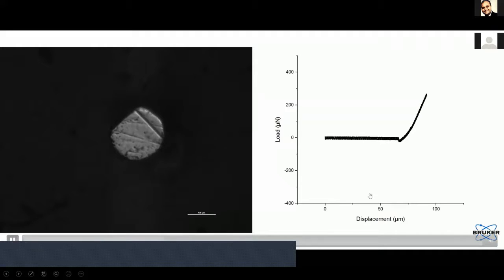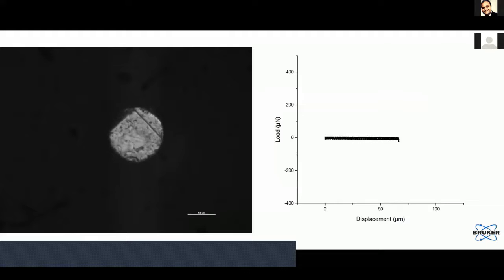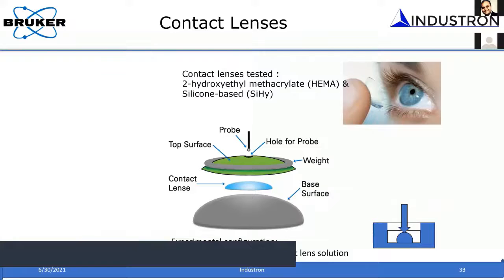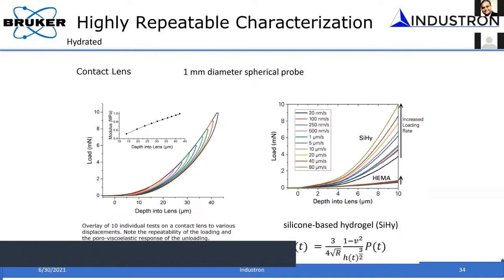So all these things that I was talking about, making a pull-off force measurement, or measuring the stiffness and calculating the property through this load displacement curve, you can still do along with this video image that we can correlate with. So that allows us to do experiments on very soft materials like contact lens. And like I said, if you do it in a liquid environment, you can avoid this adhesion problem. In those cases, these simple load displacement curves you can fit with Hertzian contact mechanics, and you can do that at different rates of loading.